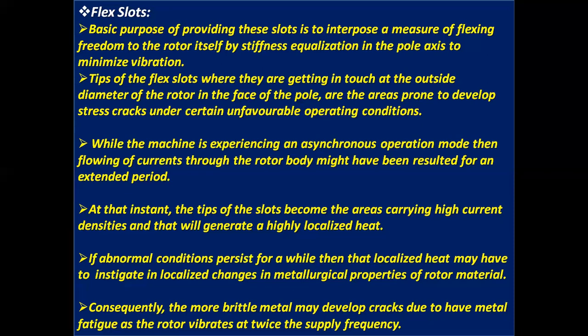At that instant, the tips of the slots become the areas carrying high current densities and that will generate highly localized heat. If abnormal conditions persist for a while, then that localized heat may instigate localized changes in the metallurgical properties of rotor material. Consequently, the more brittle metal may develop cracks due to metal fatigue as the rotor vibrates at twice the supply frequency.